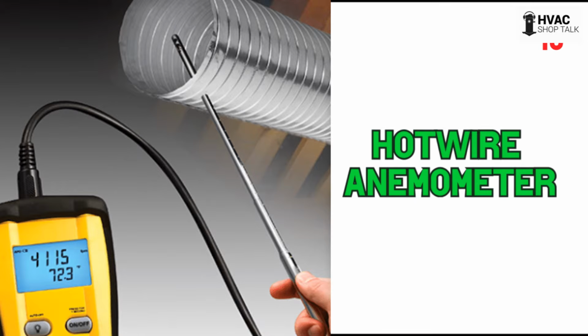So in the picture here, for the podcast people, it basically looks like a piece of spiral duct. They've cut a hole in it, and this probe is sticking through that hole. You move it across the diameter of the duct, and you may do this in 3 locations because you want a nice look all the way across that ductwork.